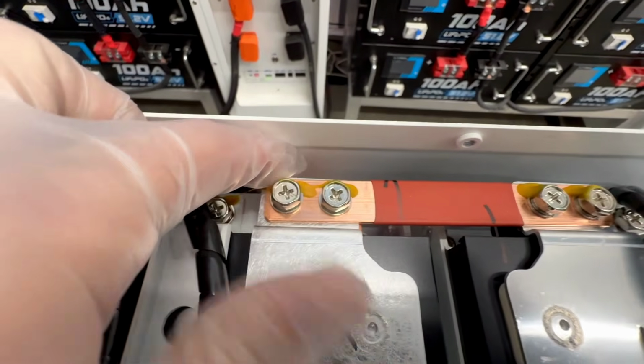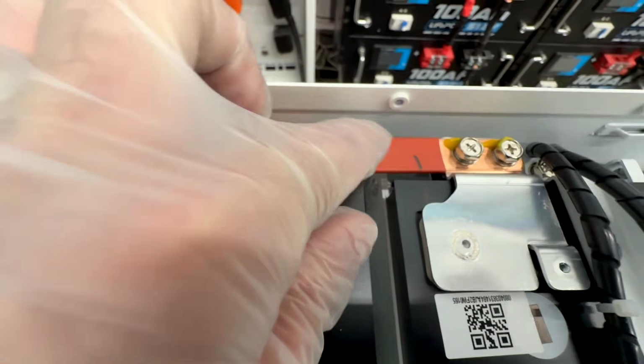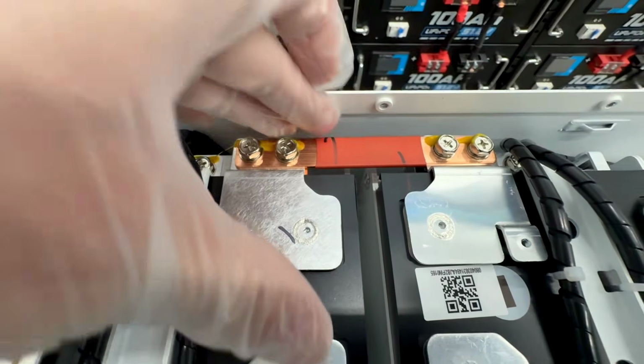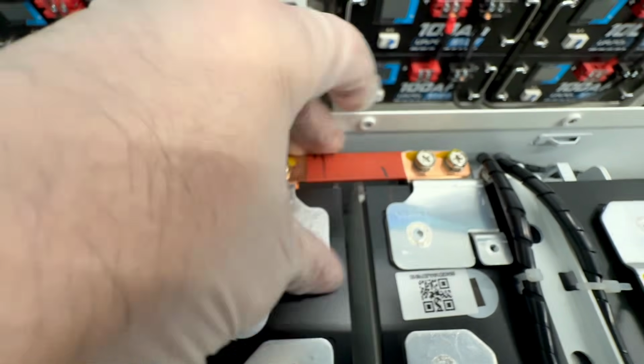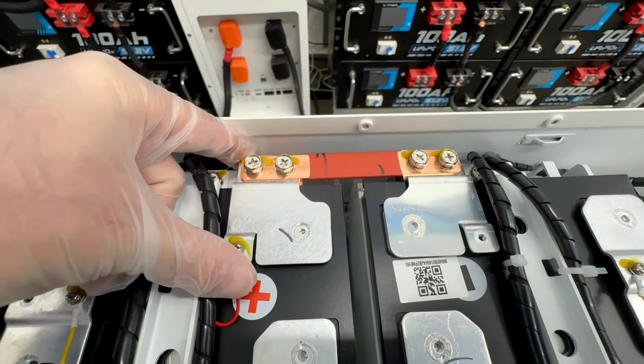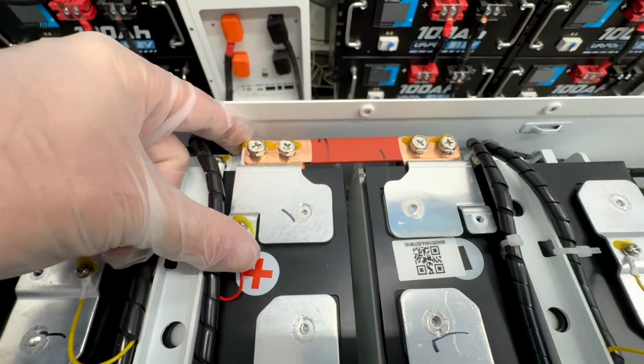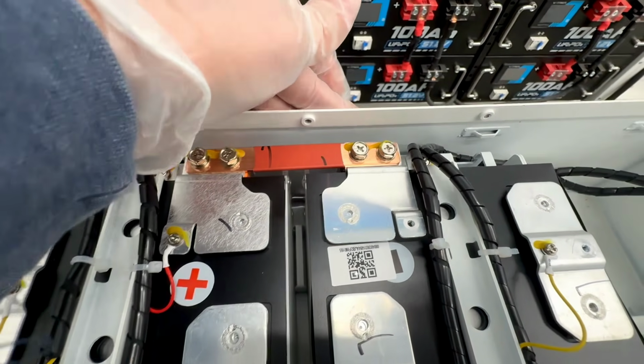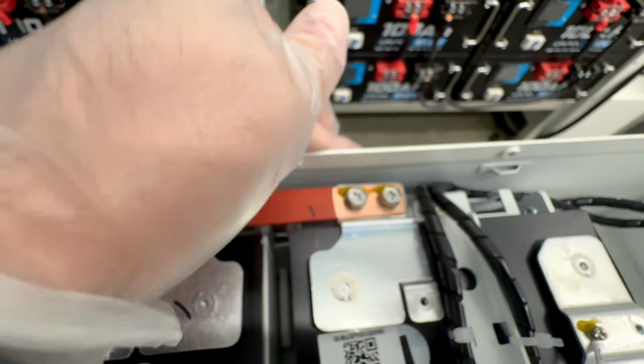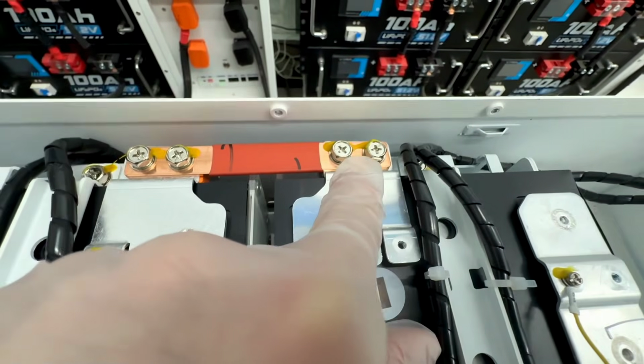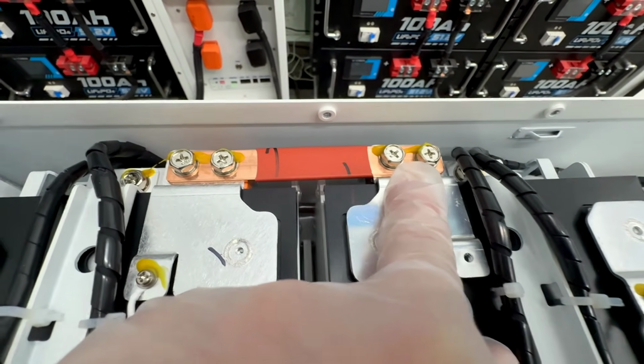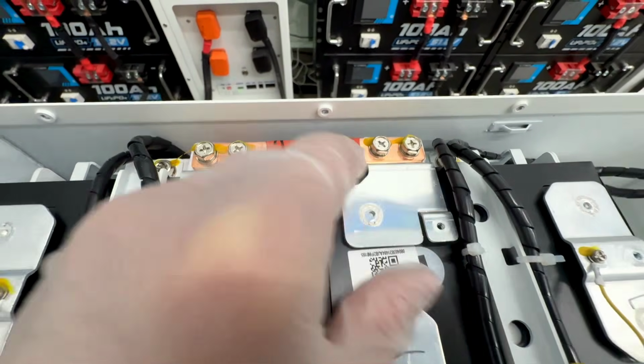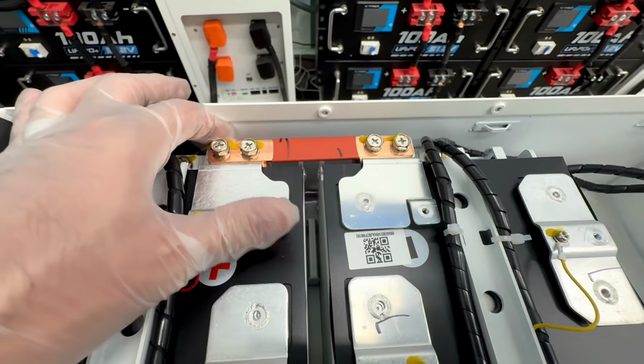However, on the back, something important to note: there is no protection for this positive bus bar. I would add either plastic back here or fiberboard. The reason is if this was dented in, as I'm moving it, it might touch those terminals and potentially short out. So that's one recommendation I would make.